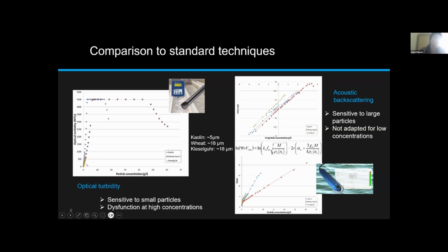So here in the first graph, you have the optical turbidity as a function of the particle concentration, measured here with a Solitax turbidity meter. And you can see, which is expected at the beginning, you have a nice proxy of suspended particles. You have a linear relationship between the concentration and the optical turbidity. But if you increase your concentration very, very highly, you have here a plateau, which shows a dysfunction of the turbidity meter. And worse, if you are still increasing your concentration, you can see that your optical turbidity meter works again and will show you a decreasing turbidity with increasing concentration.